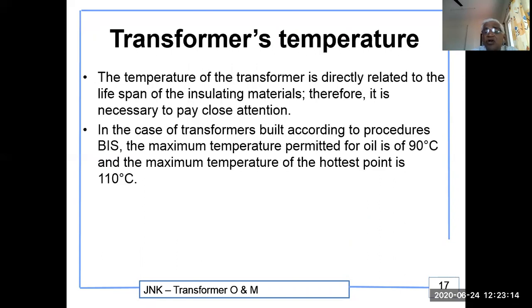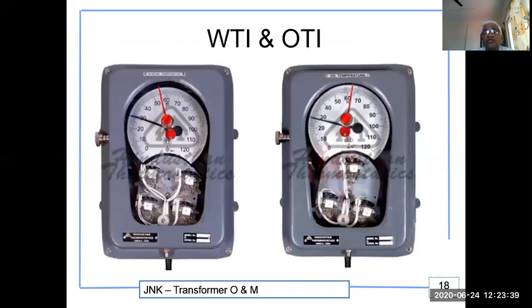The temperature of the transformer is directly related to the lifespan of the insulating material. Therefore, it is necessary to pay close attention. In case of a transformer built according to the procedures of BIS, the maximum temperature permitted for the oil is about 90 degrees centigrade, and the maximum temperature of the hottest point is 110 degrees Celsius. Now we have two meters, or you can call them gauges, shown as WTI and OTI: winding temperature indicator and oil temperature indicator.